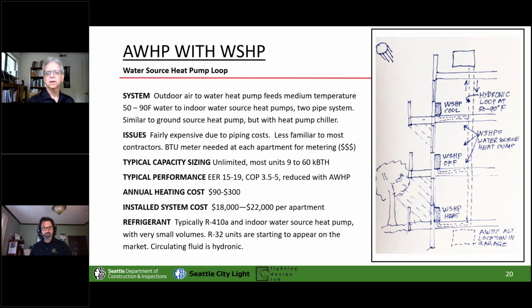Yeah, or at least reducing the volume of whatever refrigerant you're using, because your main circulating fluid is going to be water. Quick question on the water. Where would the water be stored, and how much would it be needed? It's a closed loop. So you might have a modest storage tank because it helps your chiller run better, but that storage tank will be pressurized as part of the loop.